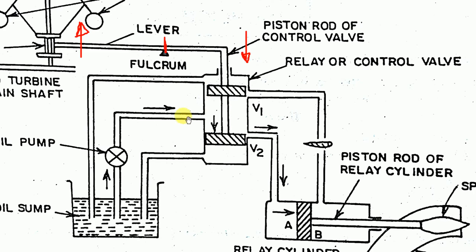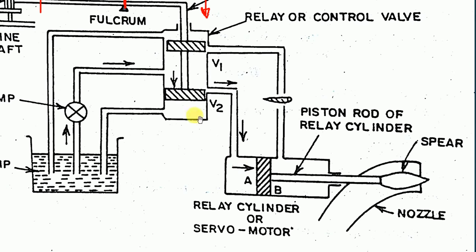The oil flows to V2 because the pistons have moved down. The oil enters into zone A — the left side portion of the servo cylinder piston. When the oil enters that portion, the force on the piston increases, and as the force on the piston increases, the spear is pushed into the nozzle. When the spear is inserted into the nozzle, the area available for water flow is reduced, so less water goes to the turbine, and the turbine speed reduces.